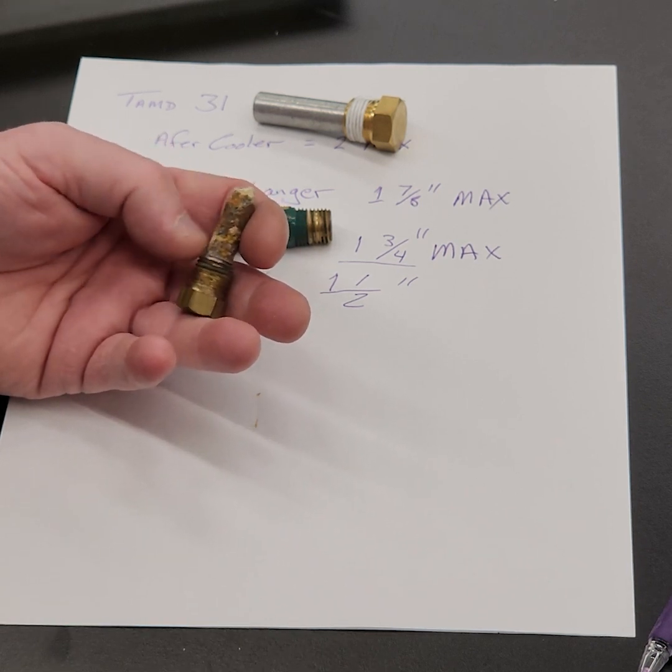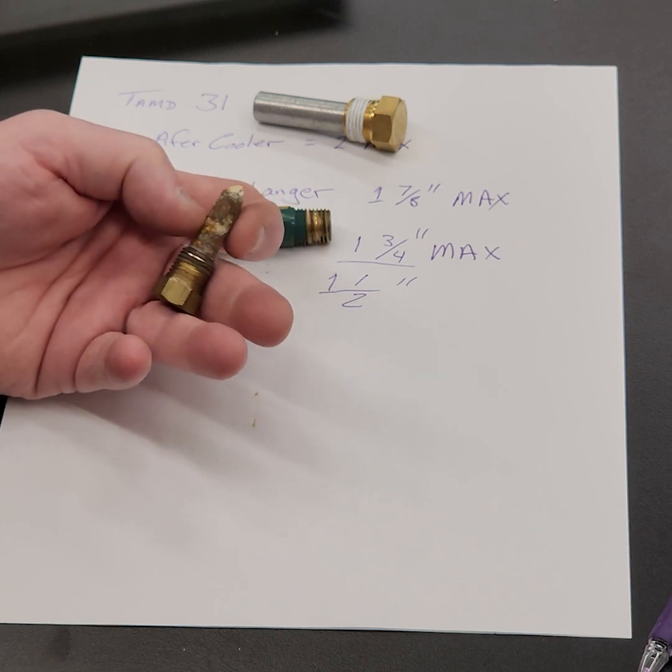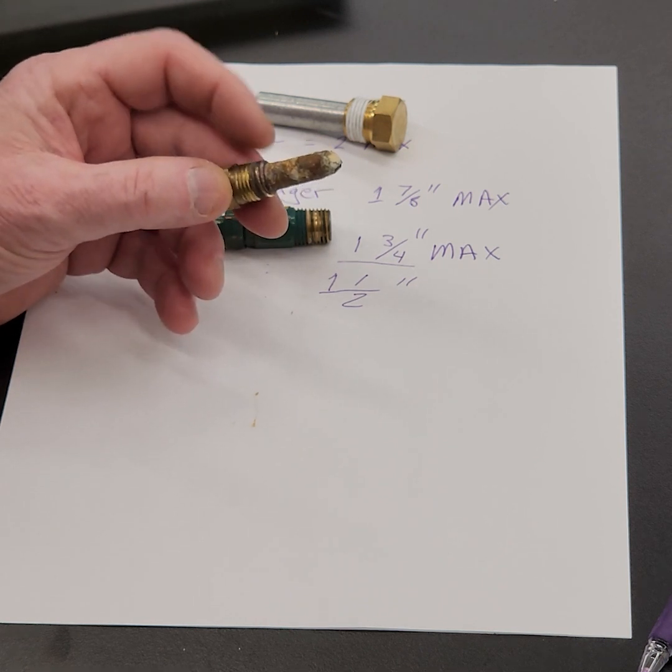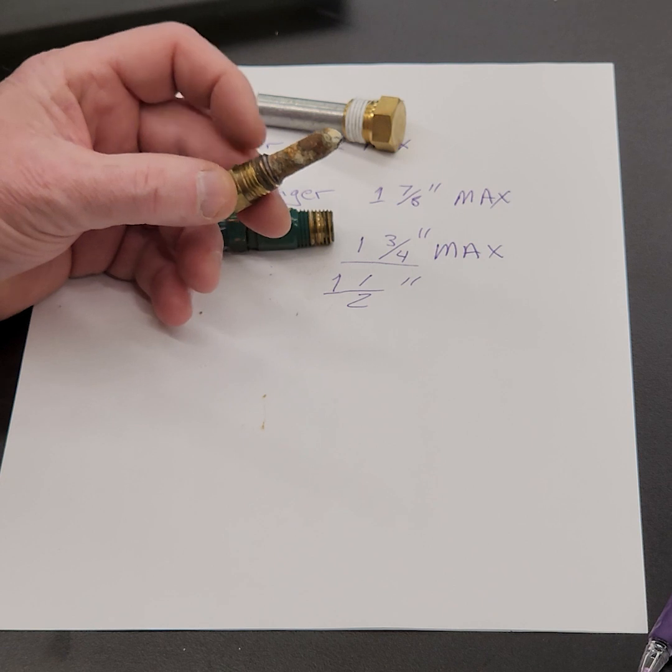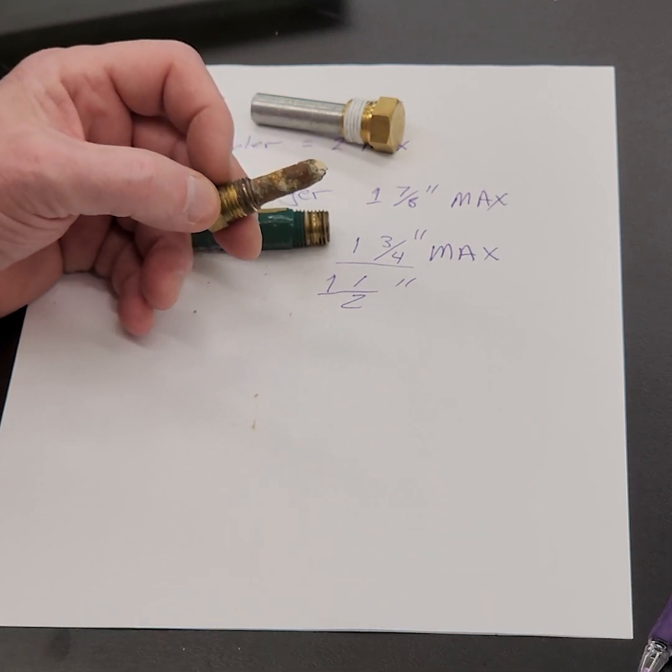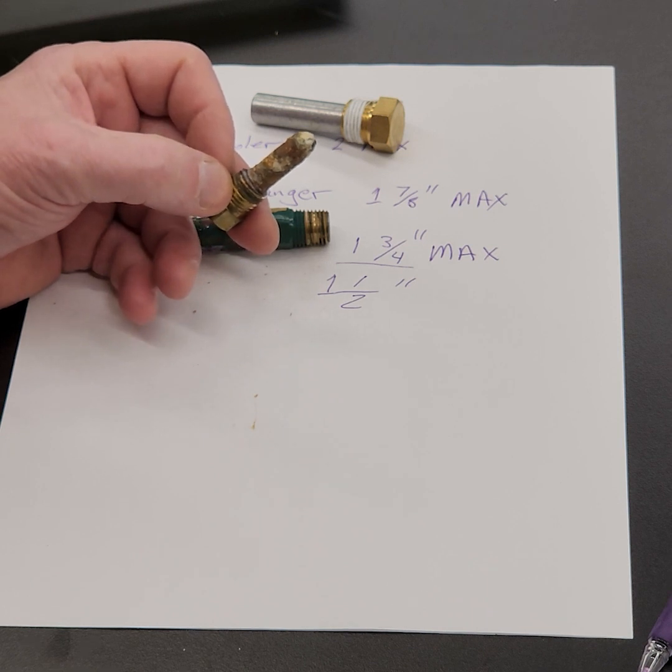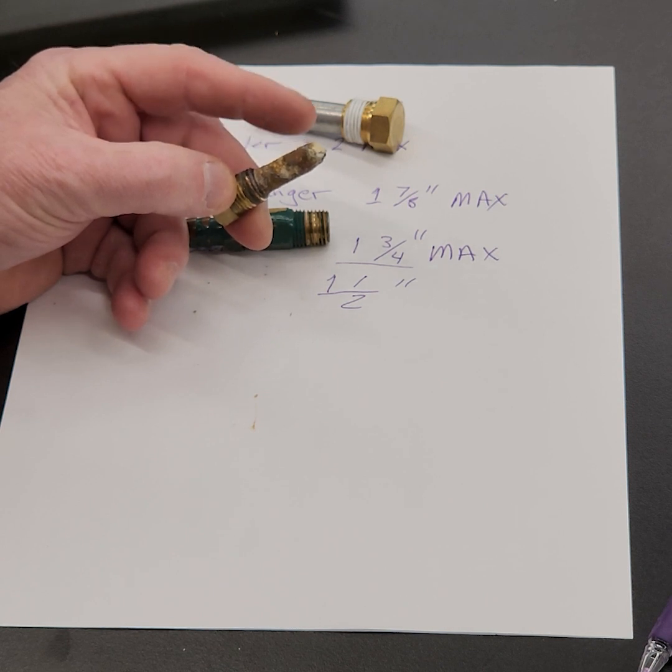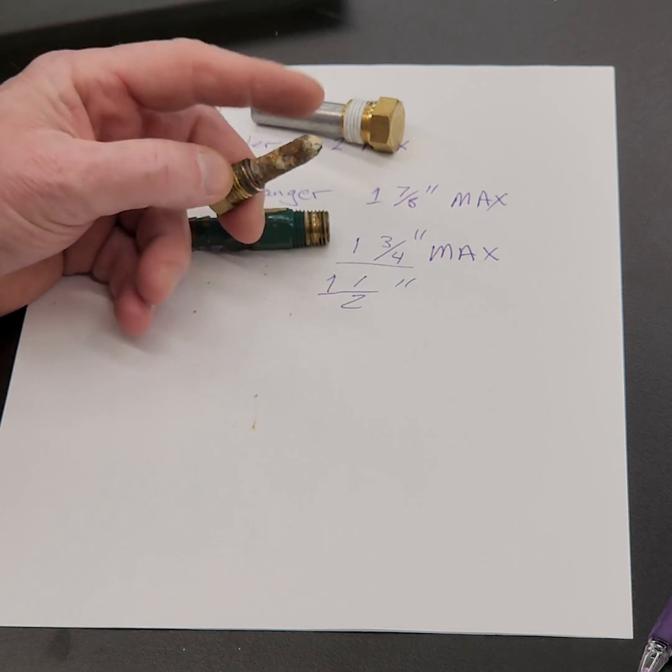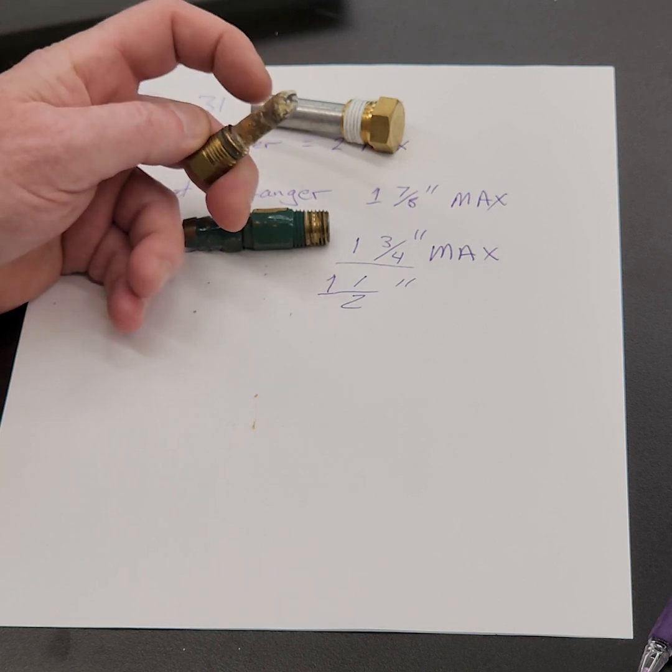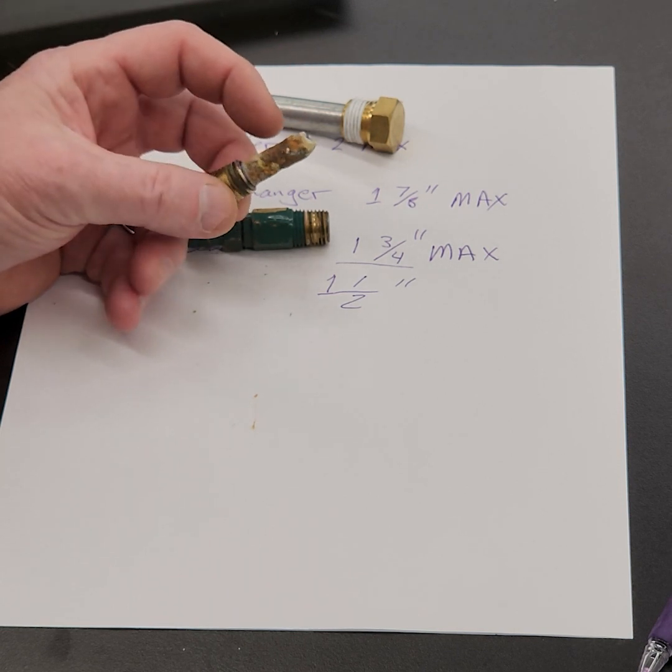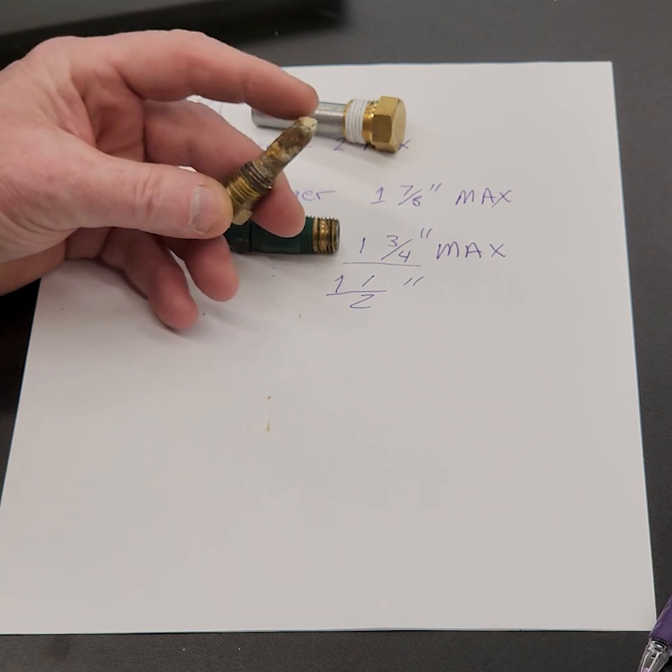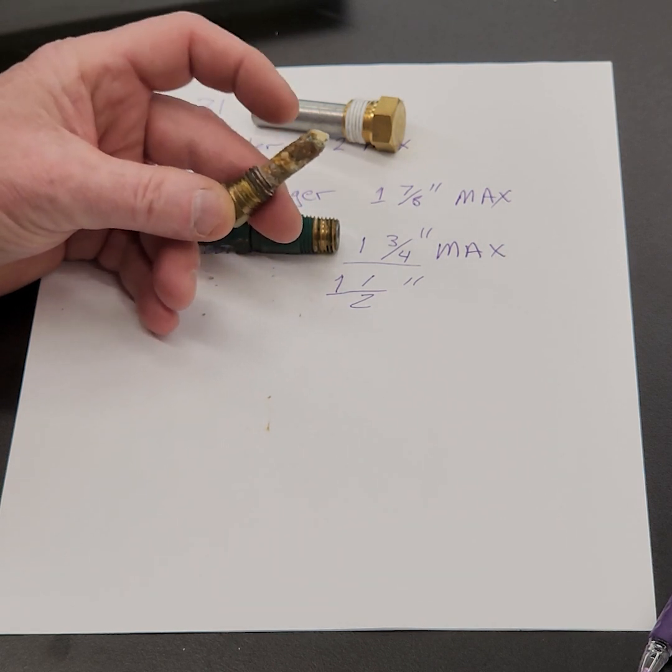The other thing is the surface of this is already corroded. So the surface has a coating on it. And that coating, if it's hard, it's not going to allow the galvanic corrosion to take place to this. So the fitting itself is made of either brass, silicon bronze, probably these are bronze fittings. The housing is silicon bronze, and the tubes are usually cupronickel. They might be copper and silver solder in older ones. This is an anode. So this is zinc. And this zinc anode is going to be more reactive than this. So it is slowly going to corrode away. If these are corroded to the surface where you have a coating, a hard brown coating on them, then I would recommend that you change them. If the size of this becomes less than half of the actual brand new size, you should change them.